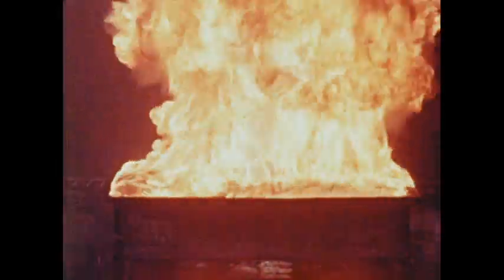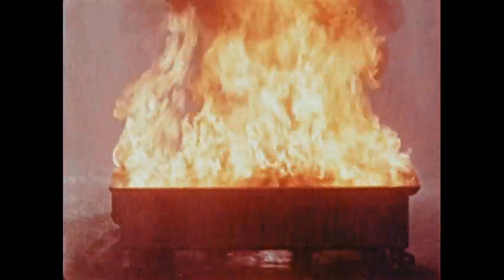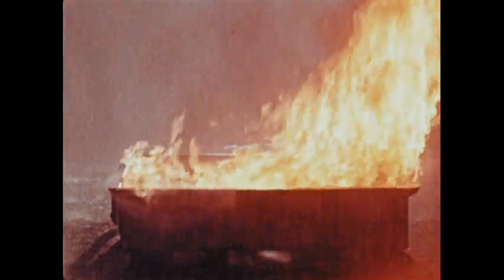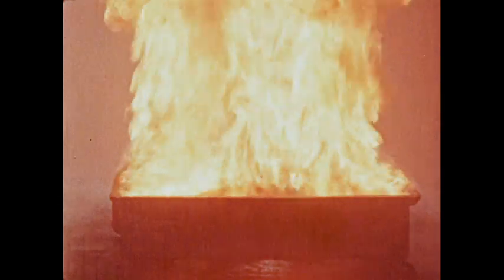Here is one of a number of fires that have started in flammable liquids and caused great destruction. The answer to preventing such fire disasters is automatic sprinklers. Sprinklers are needed over all areas where flammable liquids are used, regardless of other types of extinguishing systems. The sprinklers can't be expected to extinguish a fire in a low flash liquid, but they perform two very important functions: first, they reduce the intensity of the fire and keep the surroundings cool, preventing the fire from igniting any combustible material in the vicinity; and second, they keep the building steelwork cool, preventing buckling and collapse. If the process involves a high flash liquid like quench oil, the sprinklers will actually extinguish the fire, because the water quickly cools the oil below its flash point.